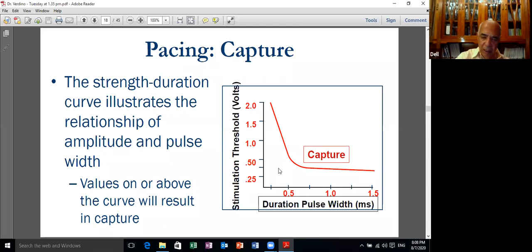And the chronaxie is the ideal time to pace the heart, ventricle, or atrium in order to save the battery power. Usually the manufacturer supplies you with a chronaxie in the range of 0.4 to 0.6, or on average 0.5 millisecond. Most of the implanters usually use the manufacturer's pulse duration, but this is the scientific basis of choosing 0.5. It's the chronaxie, which is the time required for double the rheobase to capture. You like to be up here, because anything above this line is likely to capture. You don't like to be down here. Anything below this line of the strength duration curve is not likely to capture. So it's very important to understand this part.